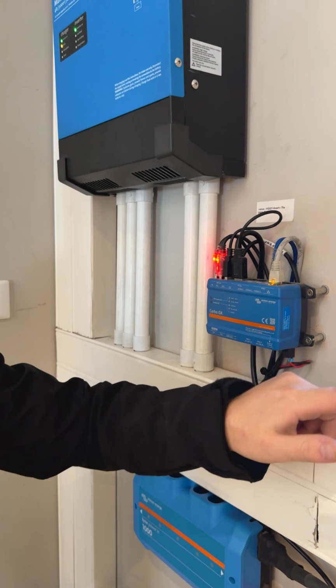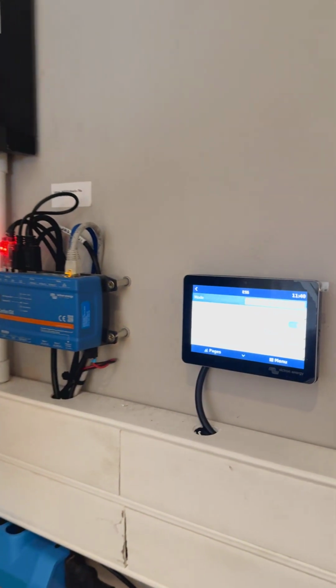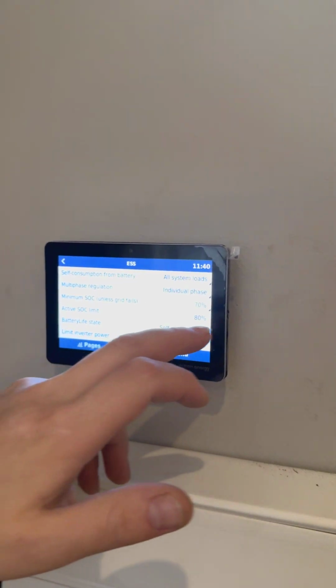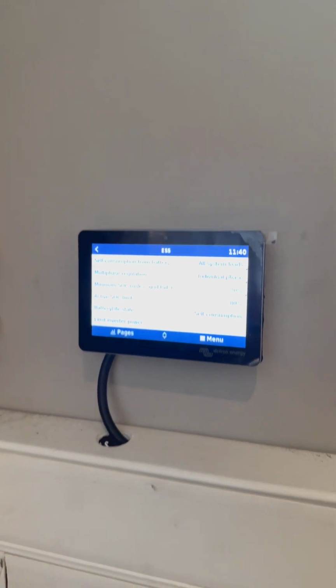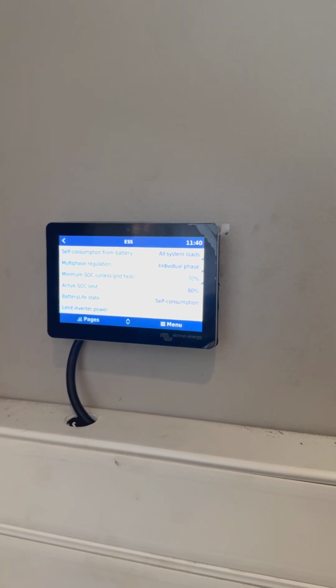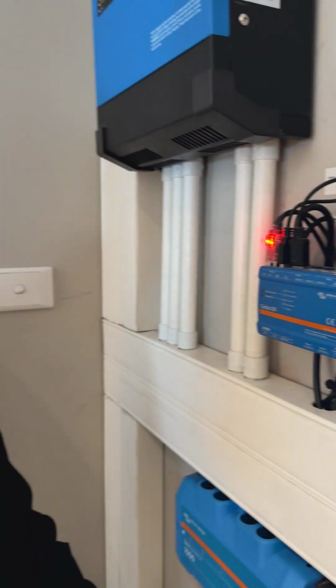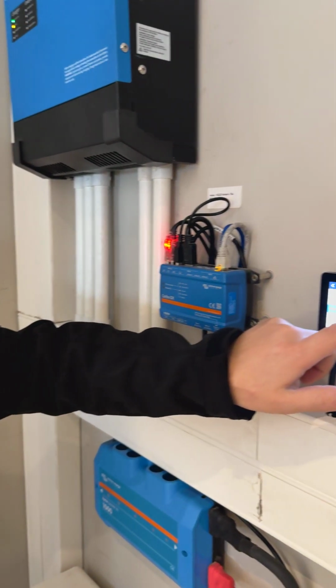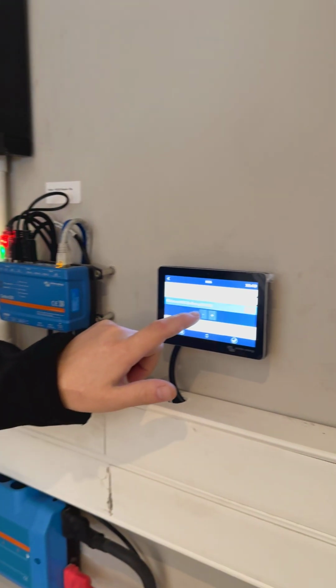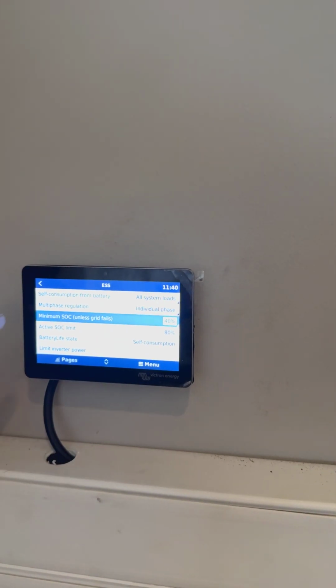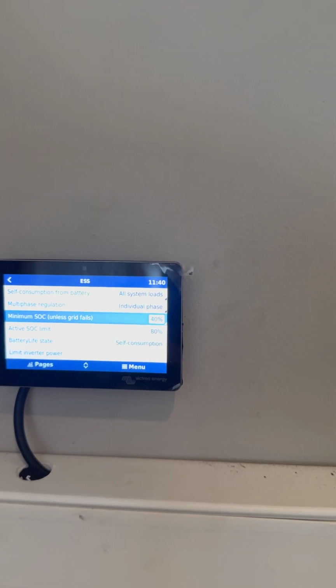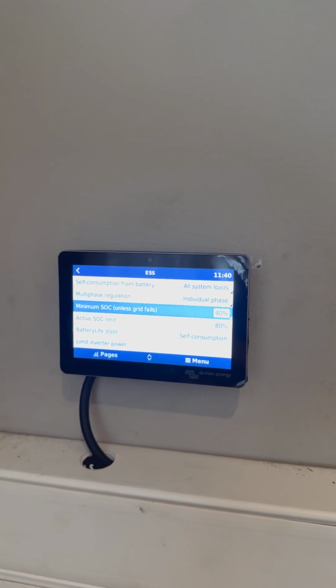If it's with battery life, it will, in most cases, so if you change it to with battery life, your BMS and your system will work together to work out an active SOC limit. So what that means is that it will notice that your battery is not getting to 100% when charging throughout the day, so it will boost your SOC limit up to 80%. So if you look on the screen, I can go all the way down and say I want it at 40%. It will tell me no, it will only keep it at 80%. So it will only discharge 20% of the battery.